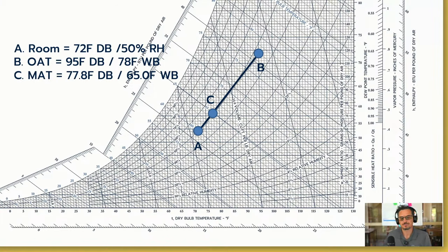That's good. Okay, so to save time, I've already plotted these out on the chart. If you're watching this, pause it and go through it. For me, learning psychrometrics, I had to learn on the paper chart. I know a lot of this is done on the computer these days. Another thing that was really helpful when I started out, and I still do this, is I carry around a couple of charts in a bag that I take to job sites. It's got my reader, my basic tools, and a psych chart. If you're new and you can read temperature and humidity, go through the process: read the outdoor air temperature and humidity, read the return air temperature and humidity, read the mixed air, the air coming off the coil, going through the fan, going through the space, and just plot it. It's a great way to learn the process of psychrometrics. Anyway, that's just my two cents. So we've got this plotted on the chart. That's step one.